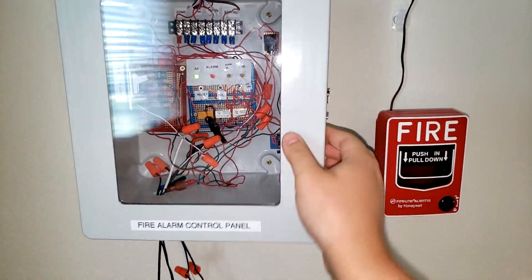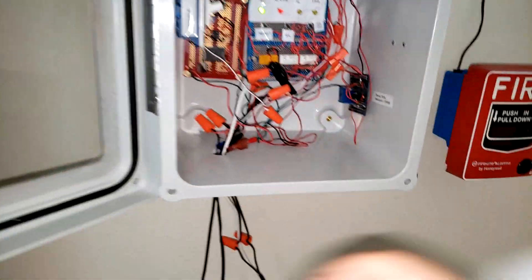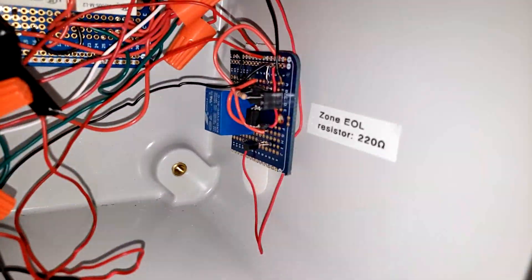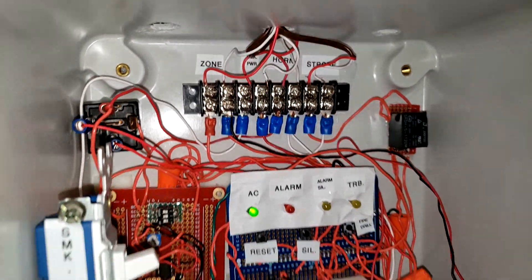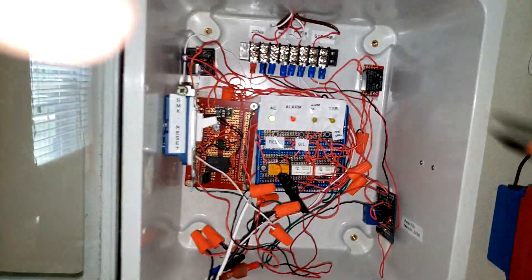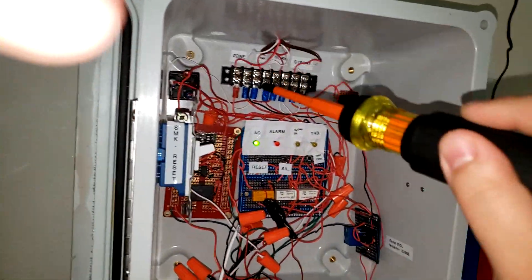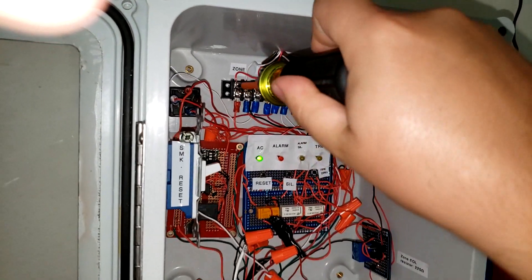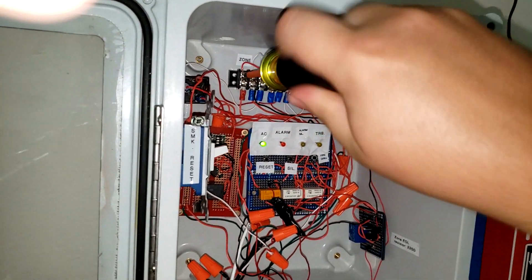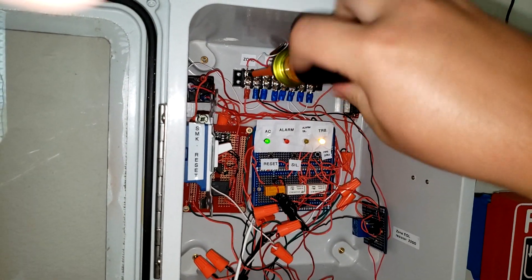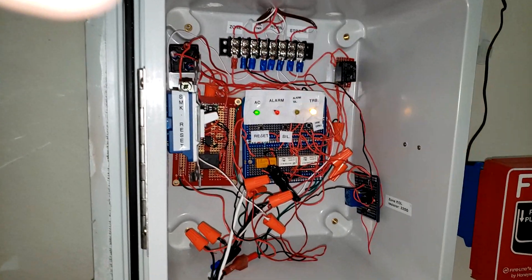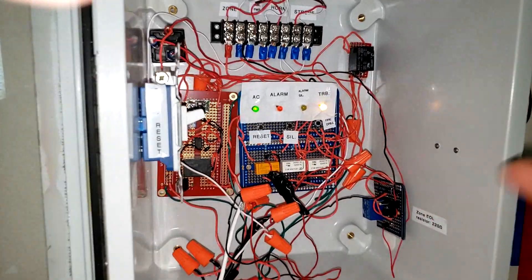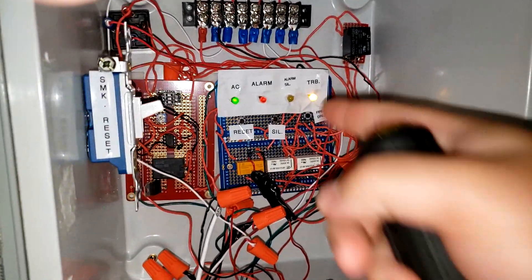Now it has a supervision circuit. I'm going to demonstrate that if this wire comes off or there's a break in the zone, the resistor isn't there, so it comes into trouble.